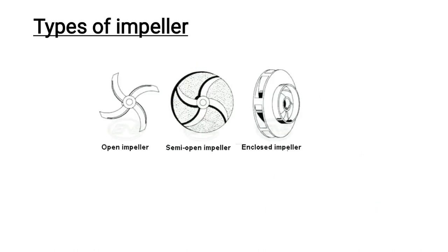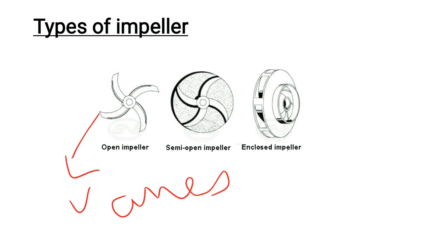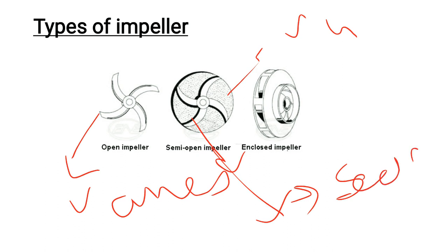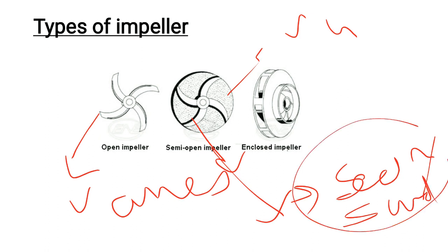There are three types of impellers: open type, semi-enclosed type, and enclosed type. In the open type, the vanes are attached only on one side with no shroud. In the semi-enclosed type, there is one shroud plate on one side. The open type impeller is used where there are sediments or sand, as it can pump such water without clogging.